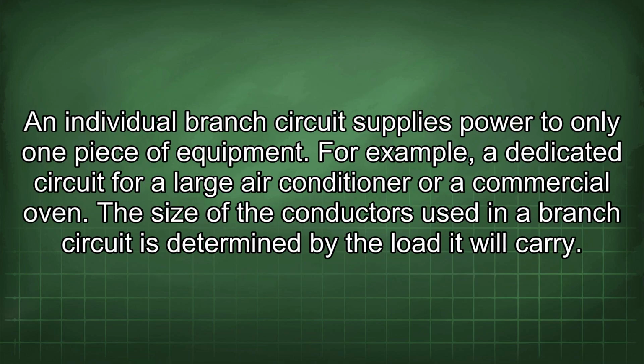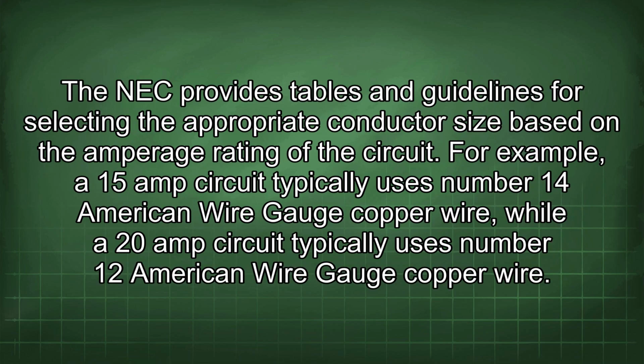An individual branch circuit supplies power to only one piece of equipment. For example, a dedicated circuit for a large air conditioner or a commercial oven. The size of the conductors used in a branch circuit is determined by the load it will carry. The NEC provides tables and guidelines for selecting the appropriate conductor size based on the amperage rating of the circuit. For example, a 15-amp circuit typically uses number 14 American wire gauge copper wire, while a 20-amp circuit typically uses number 12 American wire gauge copper wire.